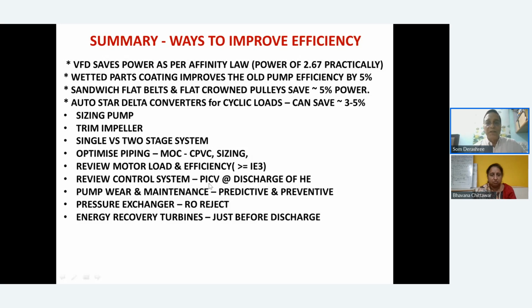Review the control system. Earlier, the machine was on the ground floor and all the consumers were on the first, second, and third floors. Invariably, the first floor consumer gets the maximum flow and the topmost floor consumer is starving. Now PICVs, pressure independent control valves, have come. Pressure will differ as you take out the fluid, and the pressure at higher elevations will be much lower, so the flow will also reduce, and again you will have imbalances in the system. For that, you have either PICVs or a discharge line.